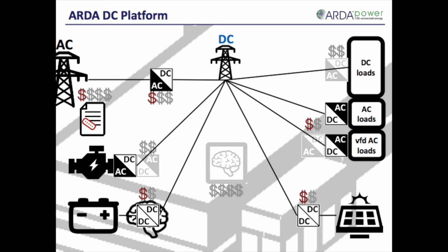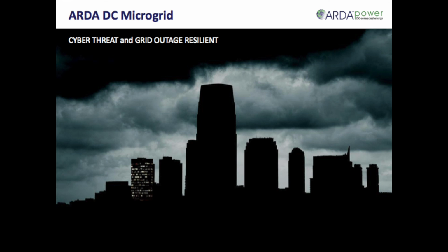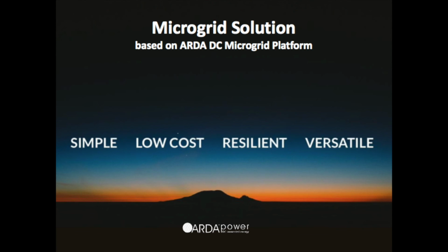ARDA's microgrid platform has a simple point of grid isolation, doesn't require a change in state to respond to grid outages, has fewer points of failure, distributed controls, and no separate wired or wireless communications network. So, independent of size, application, and configuration, you always get a very resilient and reliable system, resistant to grid faults and outages, as well as cyber threats. Welcome to the age of the plug-and-play microgrid.